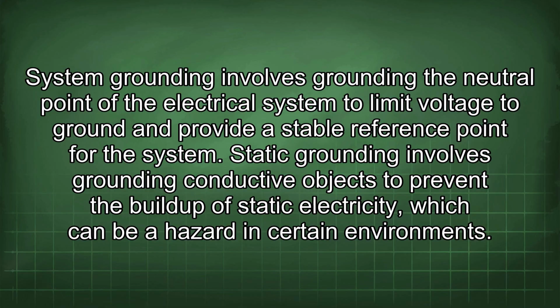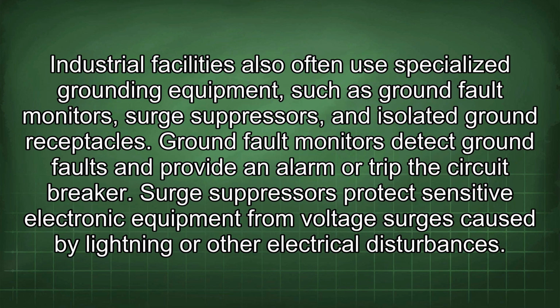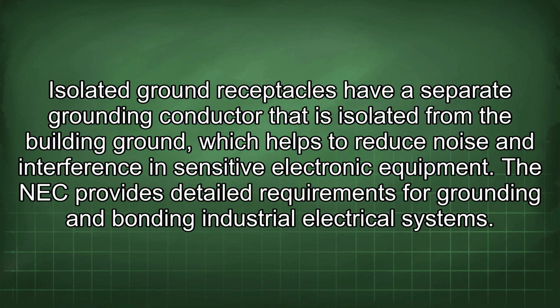Static grounding involves grounding conductive objects to prevent the buildup of static electricity, which can be a hazard in certain environments. Industrial facilities also often use specialized grounding equipment, such as ground fault monitors, surge suppressors, and isolated ground receptacles. Ground fault monitors detect ground faults and provide an alarm or trip the circuit breaker. Surge suppressors protect sensitive electronic equipment from voltage surges caused by lightning or other electrical disturbances. Isolated ground receptacles have a separate grounding conductor that is isolated from the building ground, which helps to reduce noise and interference in sensitive electronic equipment.